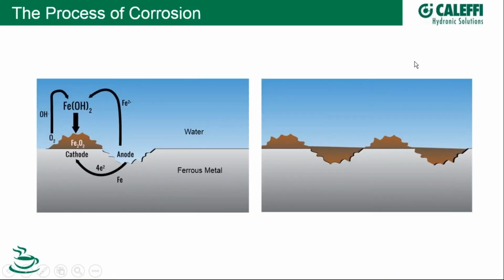Now, corrosion isn't necessarily bad. It just needs to be controlled. In fact, when iron experiences some level of corrosion, the oxide layer that builds up can act as a barrier to any further corrosion. The key thing is to keep your dissolved oxygen content to a minimum, and that's this guy right here. So what we're showing is water inside of a system touching some ferrous metal part, be it iron or steel. And dissolved oxygen is the catalyst. It's the horsepower that allows corrosion to take place, and it sets off a chain reaction of chemical reactions, if you will.